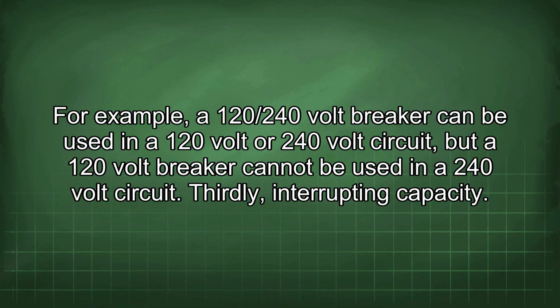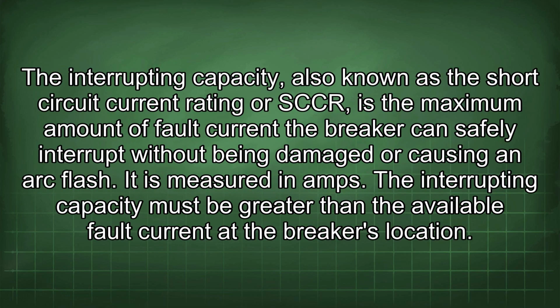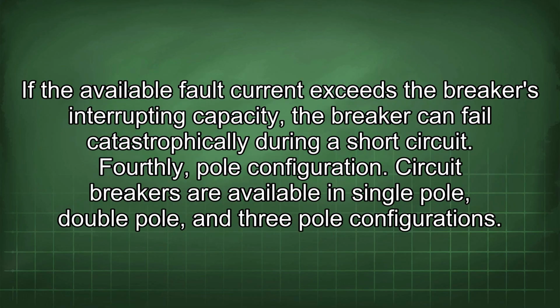Thirdly, interrupting capacity. The interrupting capacity, also known as the short circuit current rating or SCCR, is the maximum amount of fault current the breaker can safely interrupt without being damaged or causing an arc flash. It is measured in amps. The interrupting capacity must be greater than the available fault current at the breaker's location. If the available fault current exceeds the breaker's interrupting capacity, the breaker can fail catastrophically during a short circuit.